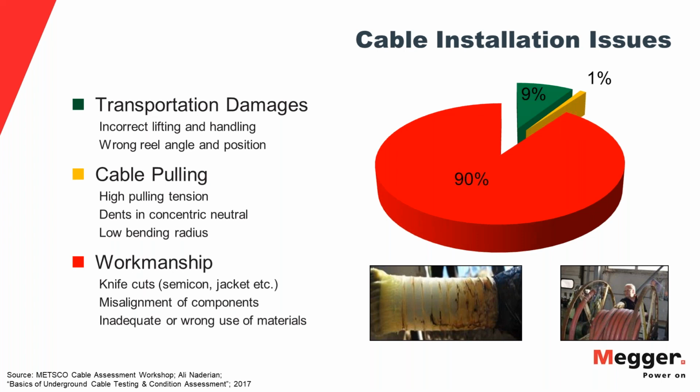My former colleague Jason always had an example, a picture which I don't have anymore, where a truck driver pretty much nailed the shipping bill onto the cable itself, damaging the sheath and the main insulation right away. I mean, sometimes it's trivial like this.